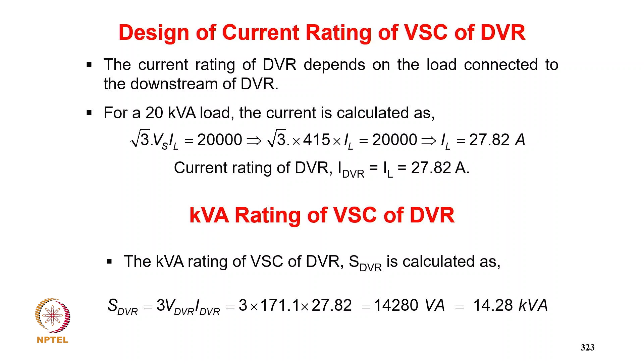Now kVA rating of the VSC for DVR. The kVA rating of the voltage source converter of DVR, SDVR, is calculated as 3 VDVR IDVR. Putting values, it comes to 14,280 VA or 14.28 kVA.